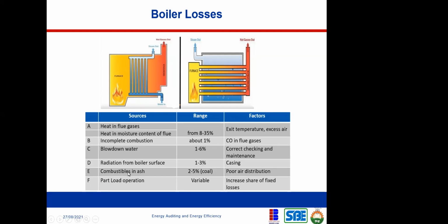Now, combustibles in ash. Now, this is where I talk about incomplete combustion. Okay, so when you've done your combustion here, you've burnt your fuel. Sometimes you find out you still have some combustibles inside the fuel, which means you have not actually finished the whole complete combustion. Okay, so it's another way of loss. So what are the factors here? Poor air distribution, which means there was not enough air for that fuel to achieve complete combustion.